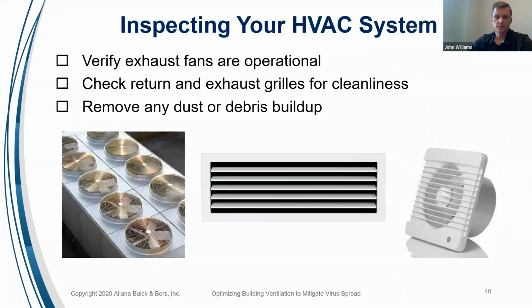Another simple item to inspect are exhaust fans. These are important, as we talked about, to remove contaminated air and to control pressurization zones. And while we're at it, we want to check our exhaust grills and return air grills. These often get caked up and restrict airflow in our buildings. They're a major point in commercial buildings for dirt and debris to collect.